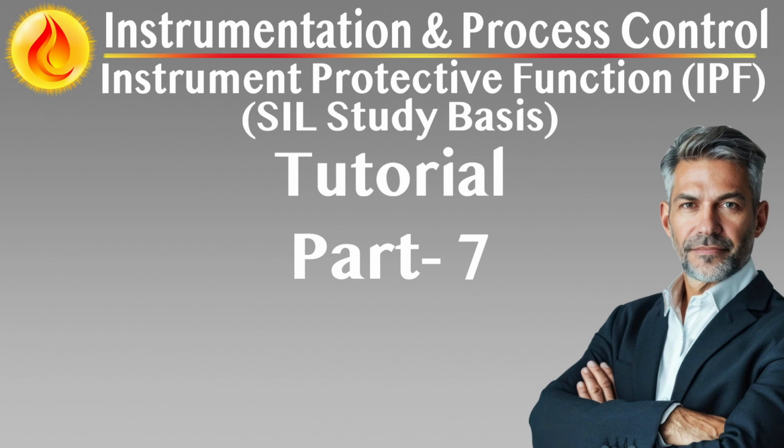Design considerations and safety impact. Diagnostic coverage must be quantified. Automatic tests contribute to safe failure fraction, SFF, and reduce the overall PFDavg, but only when their effectiveness is known, validated, and accounted for in SIL calculations.